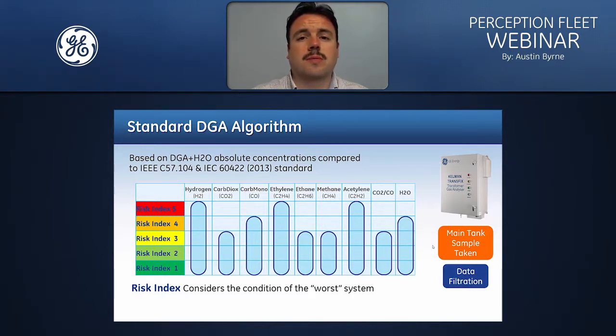So you can see in this example here, whenever the multi-gas monitor takes a sample from the main tank and performs an evaluation on the asset itself, we can see that acetylene has reached a risk index of 4, and that is purely because of the levels of acetylene that are detected within the main tank. So that asset is then considered to be at a risk index of 4.